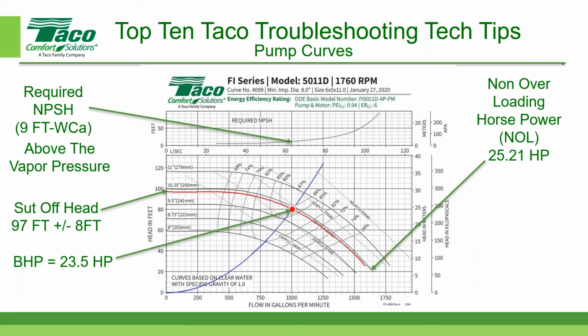I can also ask for the shutoff head. If you notice on the left-hand side here, I can ask them to do the shutoff head test. And I put in plus or minus 8 feet because the shutoff head can actually be greater or less than the published value by as much as 8 feet. So in this particular case, if they throttle back on the discharge valve, never the suction valve, always the discharge valve, and they isolate it for a few seconds, they should be able to measure the pressure differential across the pump. And in this case, the shutoff head should be around 97 feet, which will confirm that the impeller diameter is what we had originally anticipated.